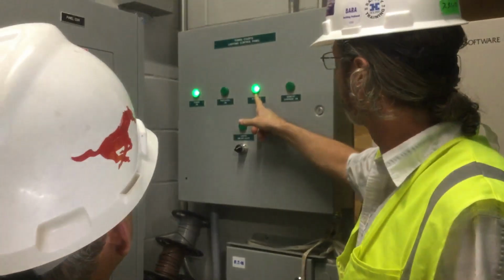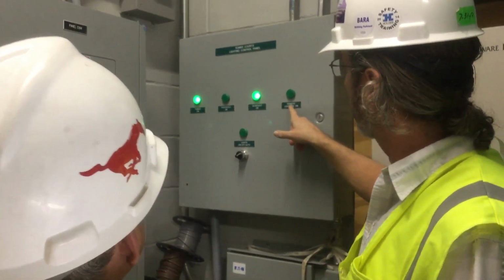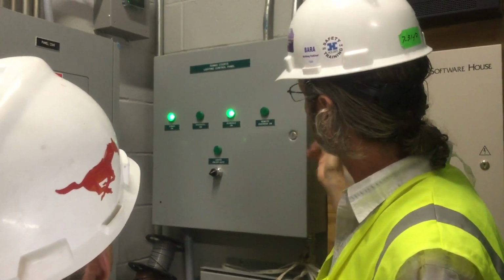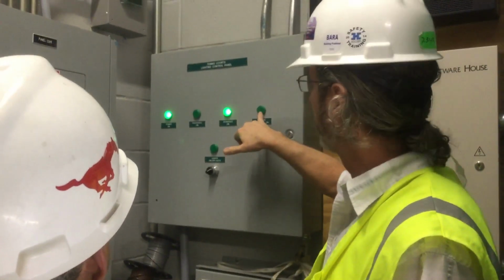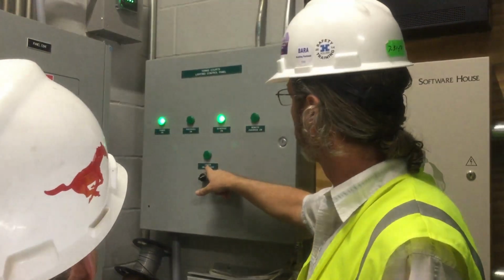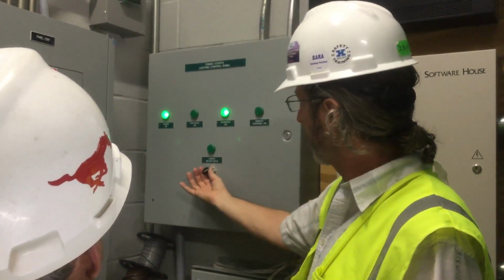And then I mentioned there's a remote override. If they come in remote through the Ethernet connection and force it on, this light pops on, and this will even override the schedule. So that's your status. Now here's your HOA switch.